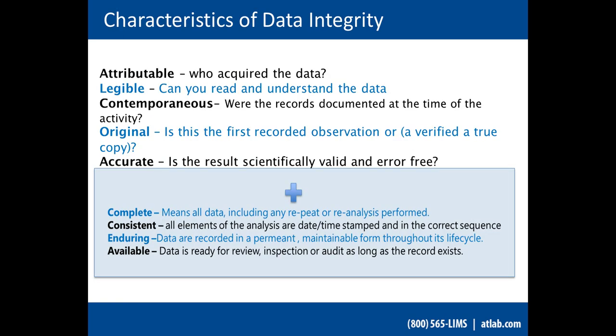ALCOA — Attributable asks who acquired the data, what are the analyst's initials and name. Legible asks whether you can read and understand the data — I've often looked at field data from people working in a plant where the writing is very difficult to interpret, like whether a number is a seven or a one. Contemporaneous asks whether records were documented at the time of the activity — computers automatically capture date and time stamps. Original asks whether this is the first recorded observation or a verified true copy. Accurate asks whether the result is scientifically valid and error-free.